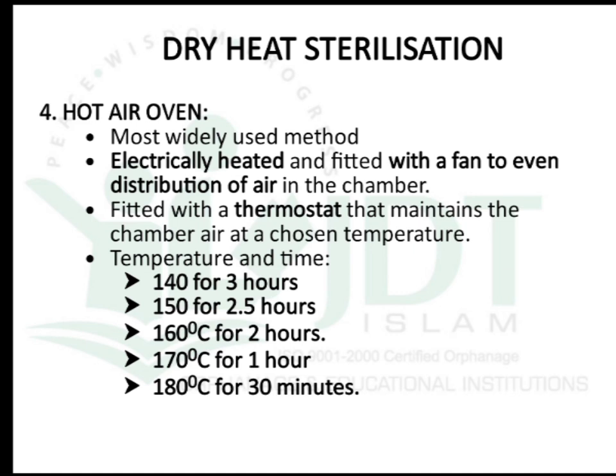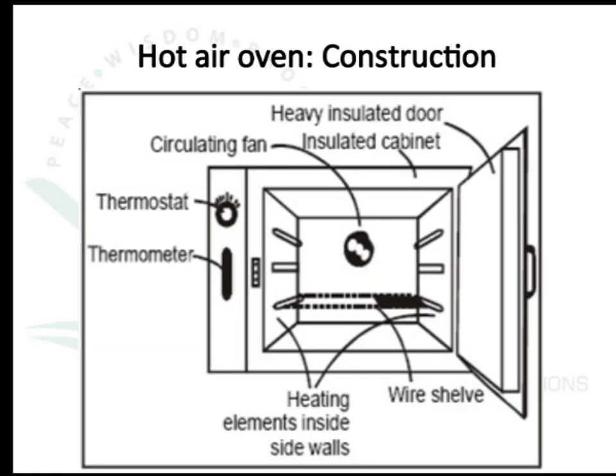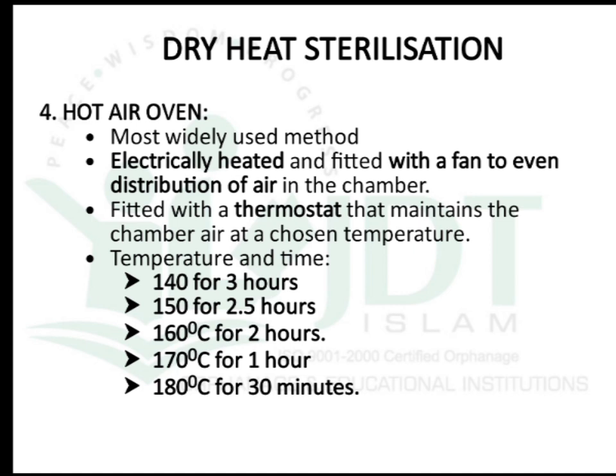The most important and most commonly used dry heat method is the hot air oven. Its construction consists of a heating element inside the sidewall, a thermometer to measure internal temperature, a thermostat to adjust temperature conditions, and a circulating fan to ensure temperature is distributed equally throughout. All of this is enclosed in an insulated cabinet with a heavy insulated door made of stainless steel or other metals.